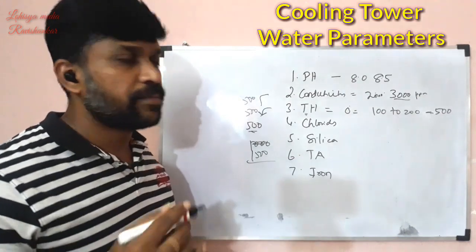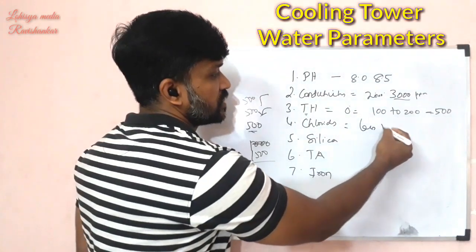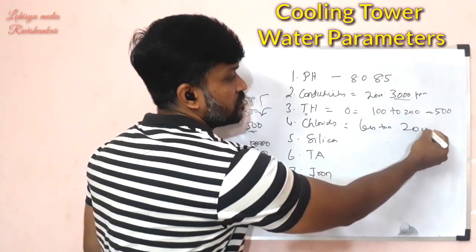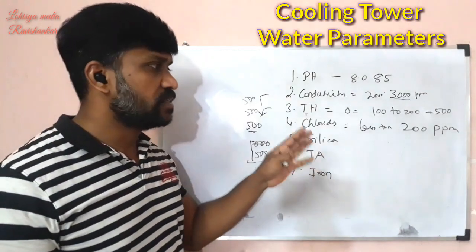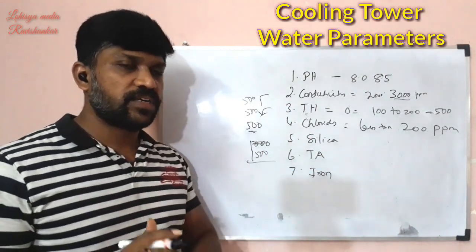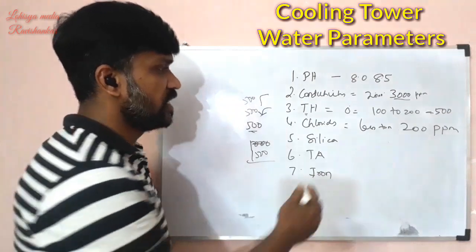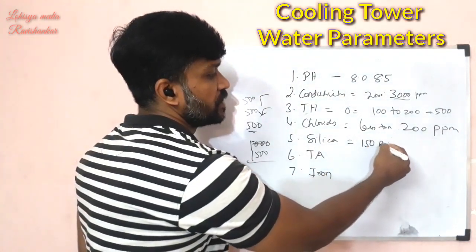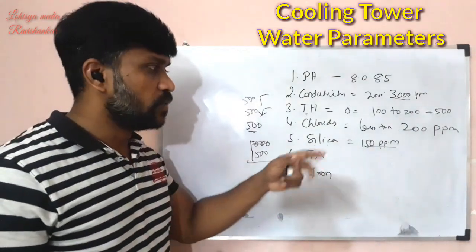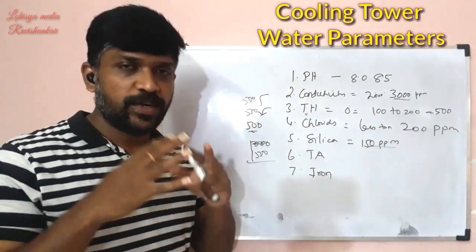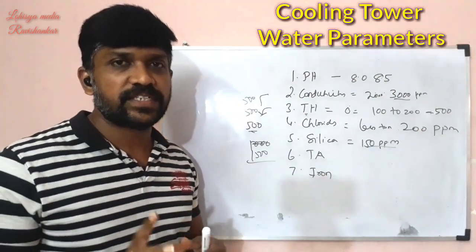For chlorides, the value should be less than 200 PPM. If chlorides exceed this, it can damage the cooling system. For silica, it should be maintained at less than 150 PPM. If silica is too high, it can cause silica scaling, which is a very difficult type of scale to remove.